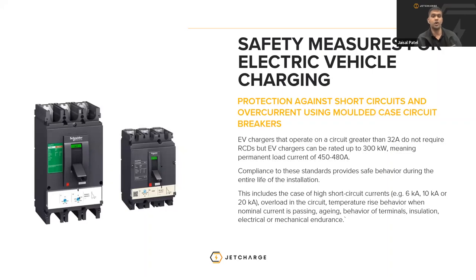As you move further up the range with DC chargers, they typically only support molded case circuit breakers, which operate on a circuit greater than 32 amps. These do not typically require an RCD, but EV chargers can also be rated up to 300 kilowatts, which means a permanent load current of 450 to 480 amps. So compliance to these standards provides safe behavior during the entire life of the installation. And obviously molded case circuit breakers would ensure that when you have high short circuit currents and temperature rise behaviors when nominal current is passing, you are essentially protecting your overall system from aging behavior of terminals, insulation, and electrical faults.